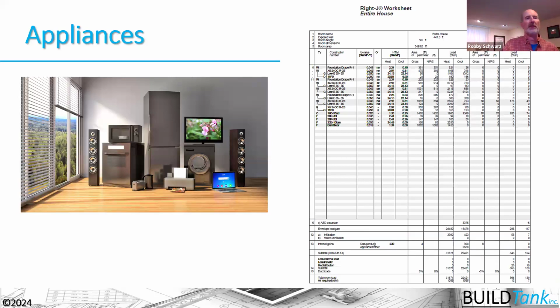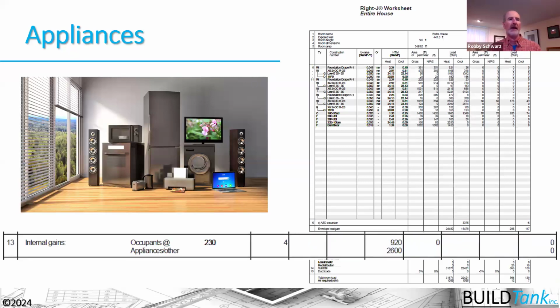Okay, so we're going to move to appliances here. So appliances also are a load, and it's called out here specifically. Internal gains, here it's telling us 2,600 BTU hours are being associated to appliances. Now, appliances are somewhere around 1,500 to 1,600 BTU hours per appliance that you add. We're really trying to take into account big appliances like refrigerators, for example, that are running pretty constantly, expelling heat into the house there, and that load needs to be taken into account.